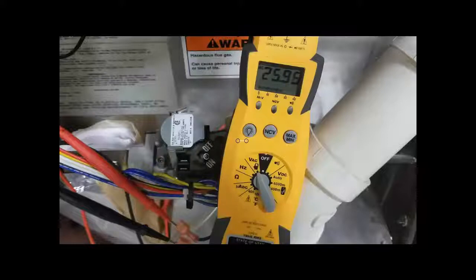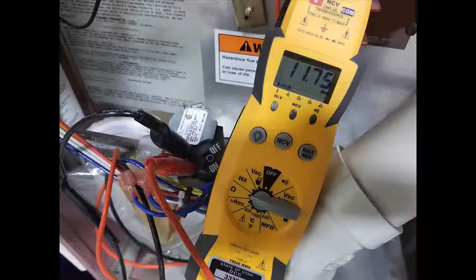So if the gas valve were not energizing like it should, then the next step would be to check the condition of the gas valve itself. All I have to do is move my meter probes up to the two terminals on the gas valve where the wires used to be. I set my meter to the ohm scale, and I'm looking for some sort of ohm reading. Generally, anywhere from 10 to 20 ohms is what you'll see. Could be more, could be a little less, just depends. But as long as you're getting a reading, you know that the windings in the gas valve are okay. If you get an open line, that's an indication that the gas valve is bad and should be replaced.